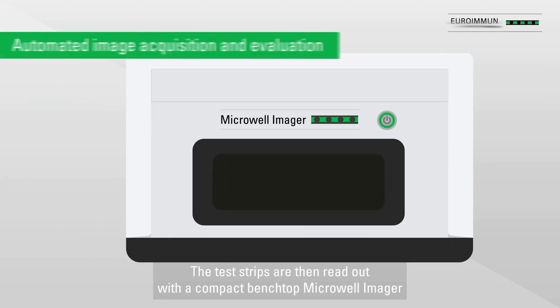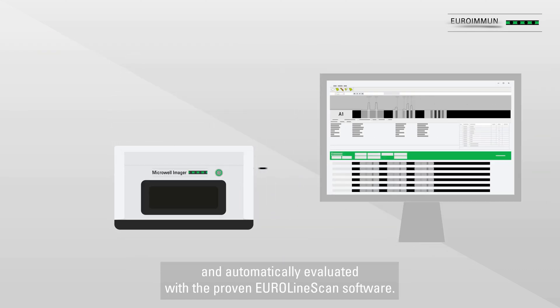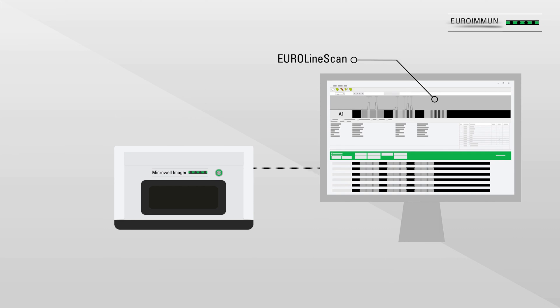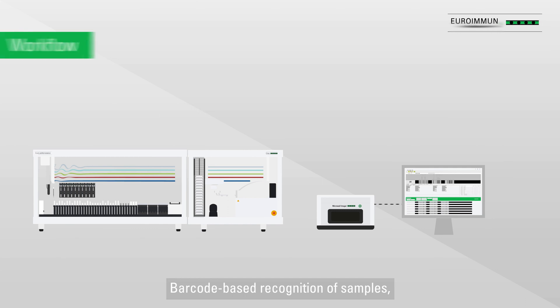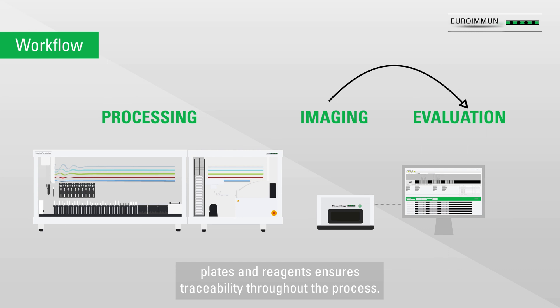The test strips are then read out with the compact benchtop Microwell Imager and automatically evaluated with the proven EuroLineScan software. Barcode-based recognition of samples, plates, and reagents ensures traceability throughout the process.